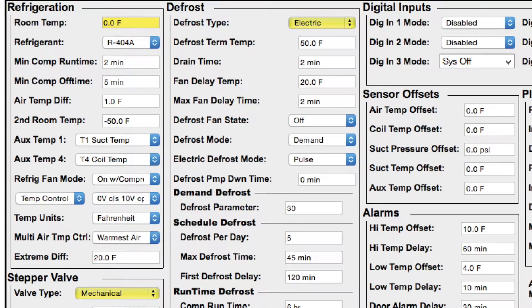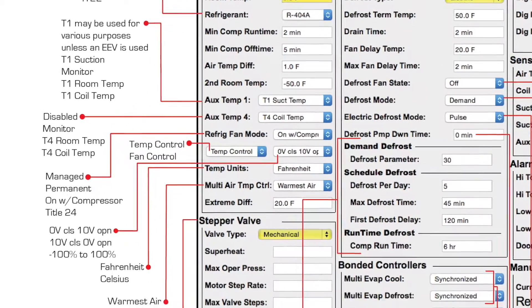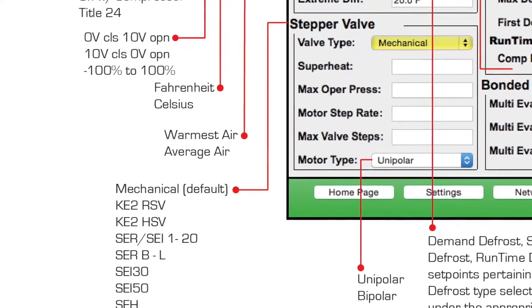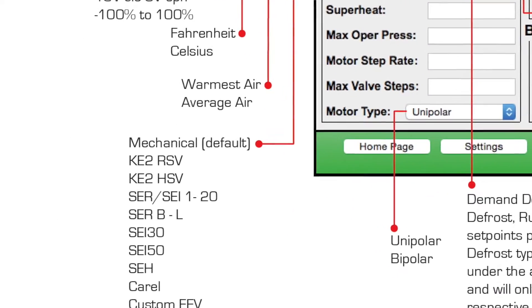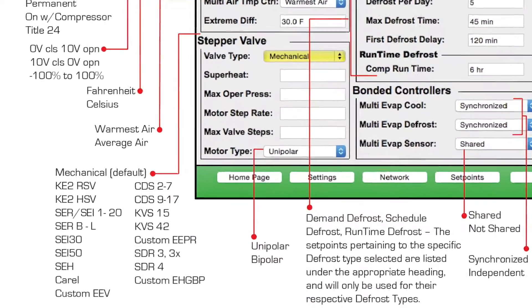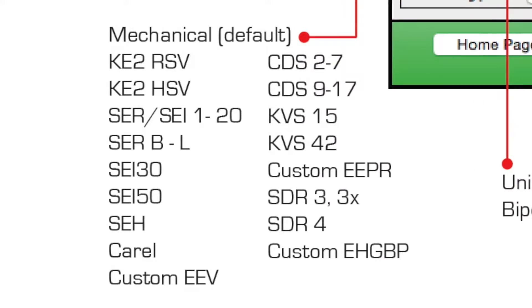We carefully considered the most likely field scenarios when establishing the defaults for each. Once the default setup is selected, the set points can be adjusted for your specific application. And while the KE2 Evap controls an electronic expansion valve, the KE2 Evap RE controls EEVs as well as electronic pressure regulating valves or electric hot gas bypass valves.